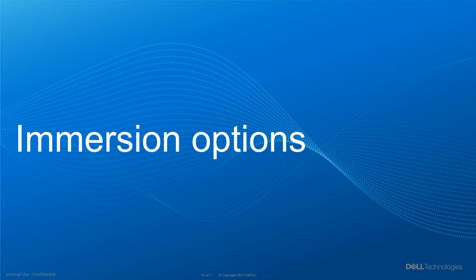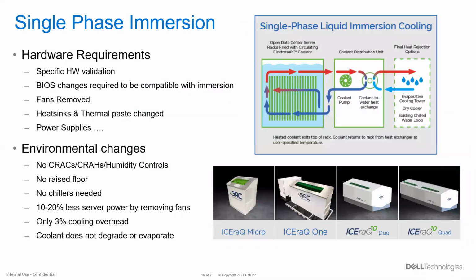As I mentioned on the first slide, where I talked about advanced cooling solutions, we do have partnerships with companies that do immersion cooling. You may have heard of single phase immersion. What this means is the IT is immersed in a dielectric material that allows for full heat capture, as opposed to just having cold plates on CPU, GPU or memory.